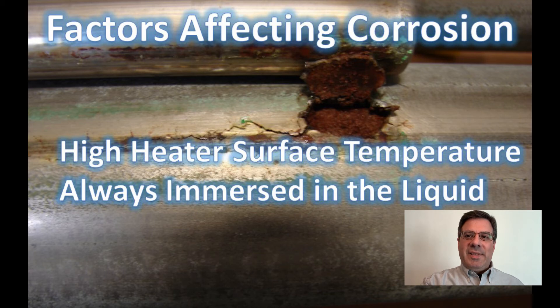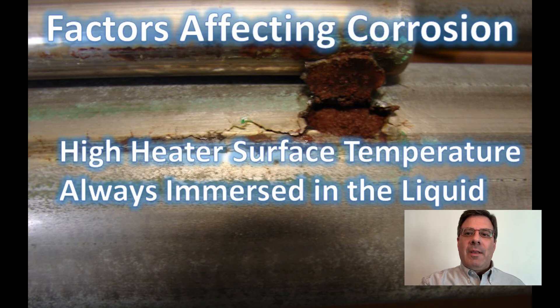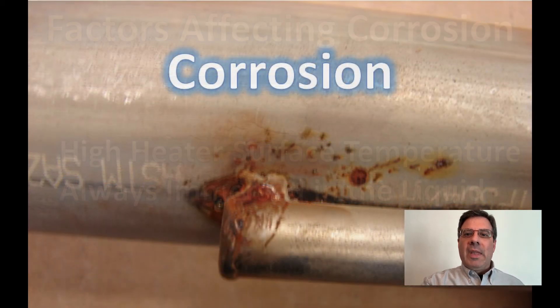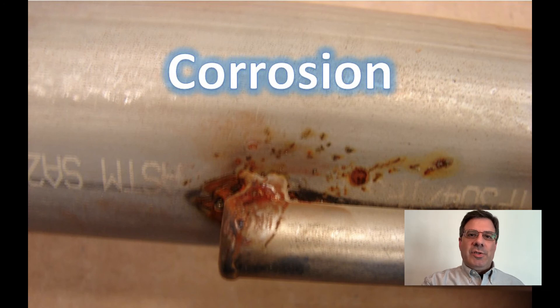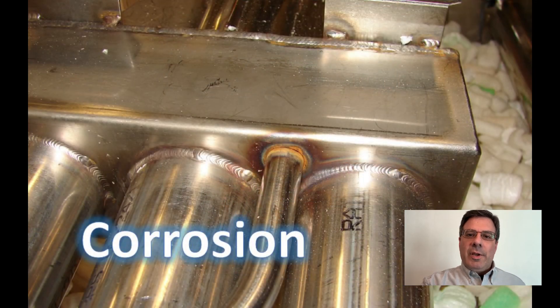Second is the time in the tank. Steel parts are only in the passivation bath for a short time, but the heater is in the tank all the time. When you put those two factors together, stainless steel may be subject to suffer corrosion over time. Process Technology recommends using a quartz or a fluoropolymer covered immersion heater for a passivation tank, as those materials are going to be resistant to the chemical at any concentration.